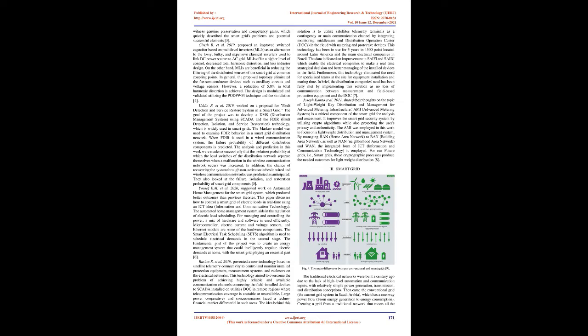6. Burian et al. 2019 presented a new technology based on satellite telemetry connectivity to control and monitor installed protection equipment, measurement systems, and reclosers on the electrical networks. This technology aimed to overcome the problem of achieving highly reliable and available communication channels connecting the field-installed devices to SCADA installed on utilities' DOCs in remote regions where telecommunication coverage is unstable or unavailable. Large power cooperatives and concessionaires faced a techno-financial market differential in such areas.